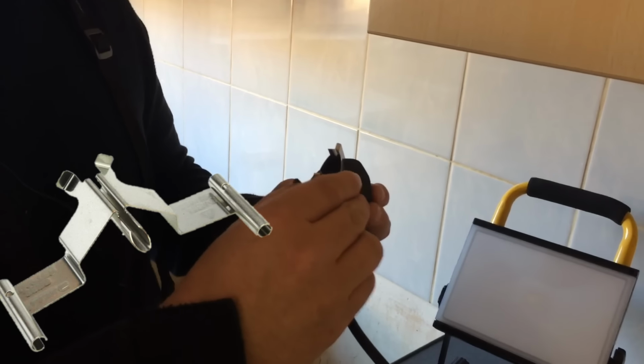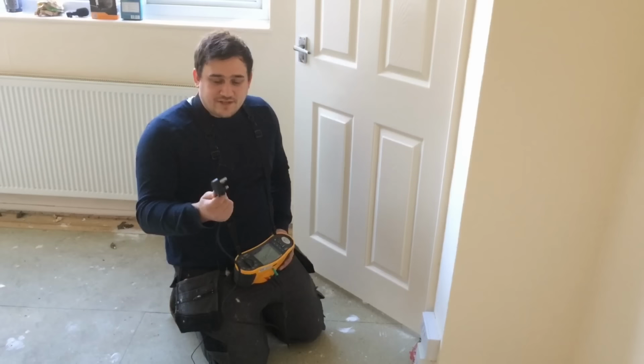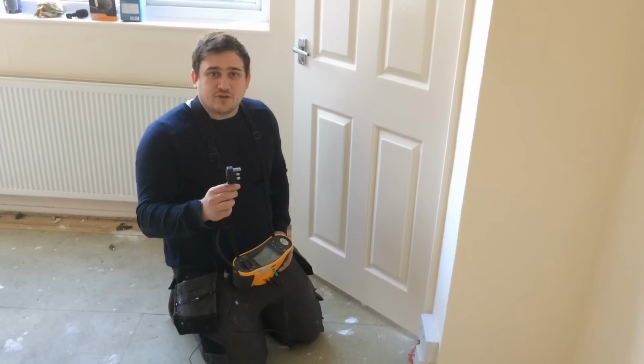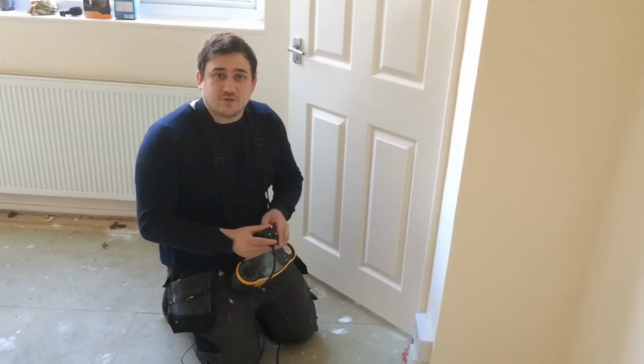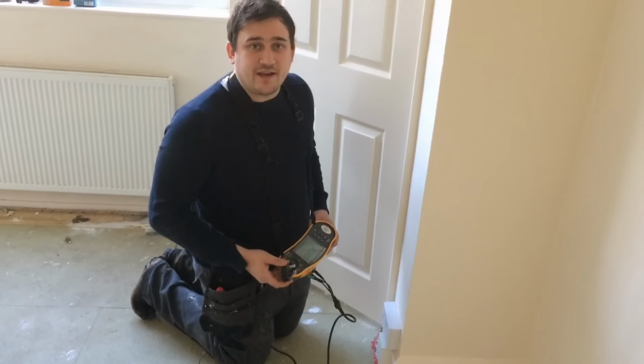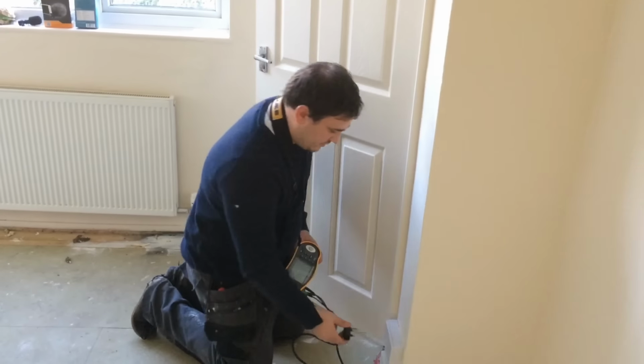I've got this bit of kit here. You simply click it on, just between the line and neutral, as that's what I'm testing between. So I've used the blue and red into the back of the tester. Now I've zeroed my leads, I'm going to go around to all of the socket outlets on this ring and plug into each socket, proving polarity and continuity, part polarity, part continuity on the way.